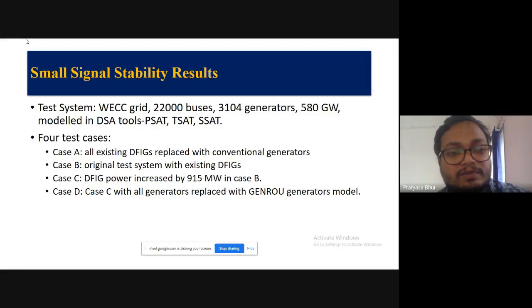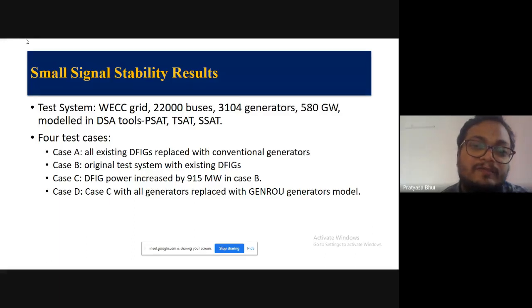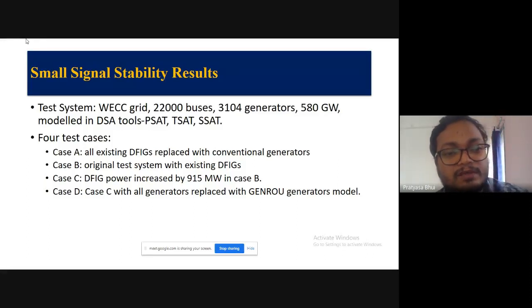The test case was the WECC grid with 22,000 buses and 3,000 generators. Total generation was around 580 gigawatts, and it was modeled in DSA tools: a steady state analysis tool, a transient stability analysis tool for transient stability analysis, and a small signal analysis tool for small signal stability analysis. So there are 4 test cases. Case B is the original test case with existing DFIGs. Case A is where all existing DFIGs are replaced with conventional generators, typically GENROU generators, round rotor synchronous generators.